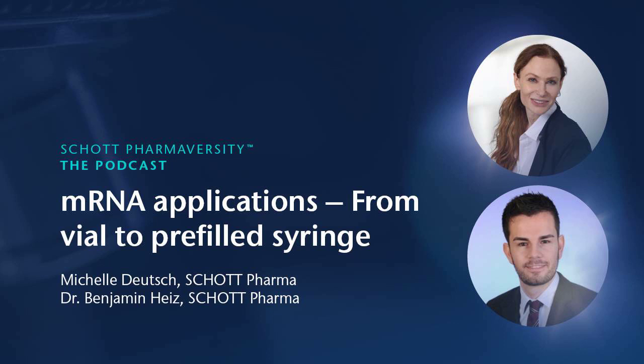Another very crucial topic is related to plunger movement. Imagine you have a prefilled syringe placed at an extremely low temperature — the liquid freezes, expands, and consequently applies a significant force on the plunger stopper, which tends to move to find an equilibrium state, depending on parameters such as filling volume, filling medium, and headspace volume. This represents a critical challenge: ensuring that the plunger displacement remains within the sterile area to maintain sterility of the filling and ensure patient safety. These are the key questions that need clear answers to supply customers with the right primary packaging for mRNA applications.